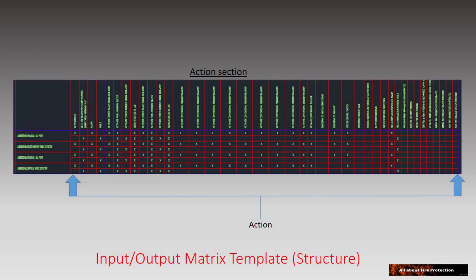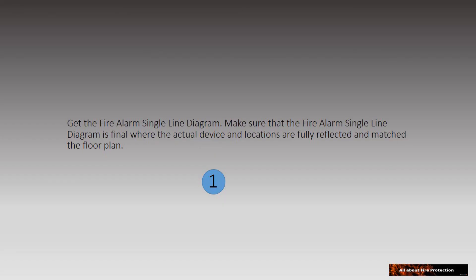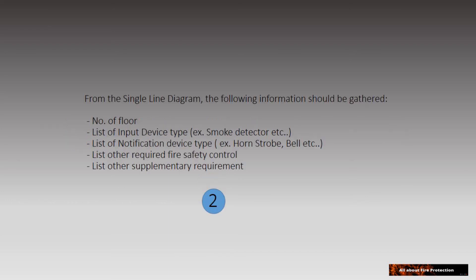In the action section, you simply mark with an X the required event as per the sequence of operation. Now let's proceed with the procedure. Step one: refer to the fire alarm single line diagram and make sure it is already coordinated and matches the plan drawings. Step two: gather all required information to fill in the input and output section, such as the number of floors, list of input device types, list of notification device types, list of required fire safety controls, and list of supplementary requirements.